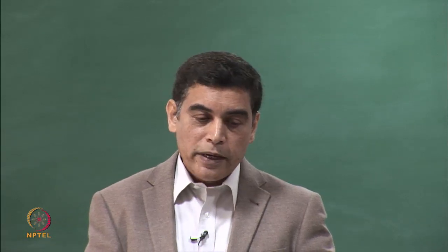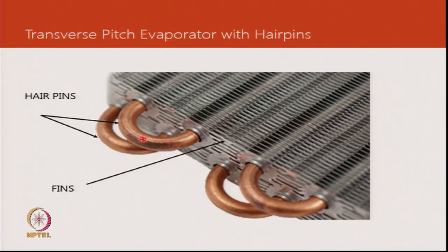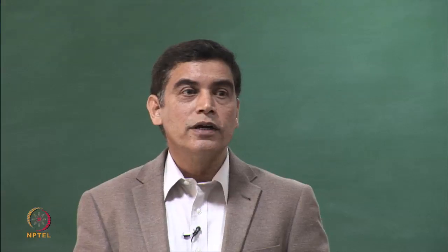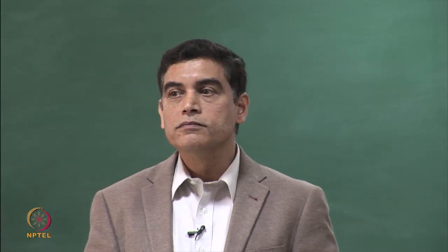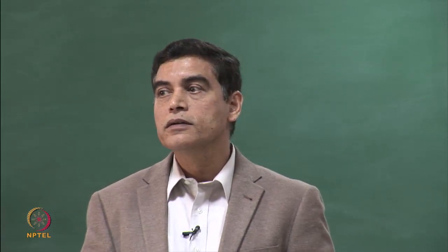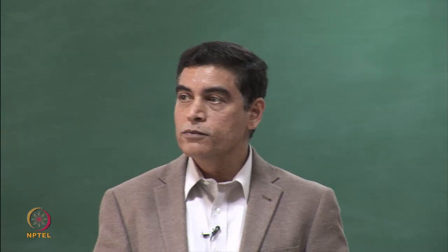Weaknesses can develop when bending the hairpin — the outer part can thin during bending, and this wall thickness reduction could compromise the strength it can withstand. For condensers especially, this must not lead to a burst or hairpin leak and consequent loss of performance.